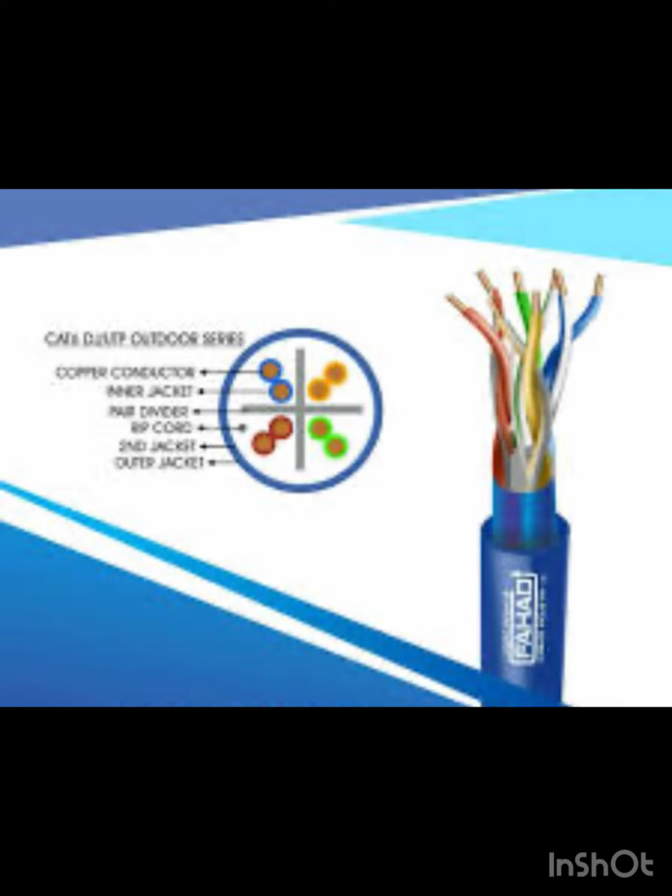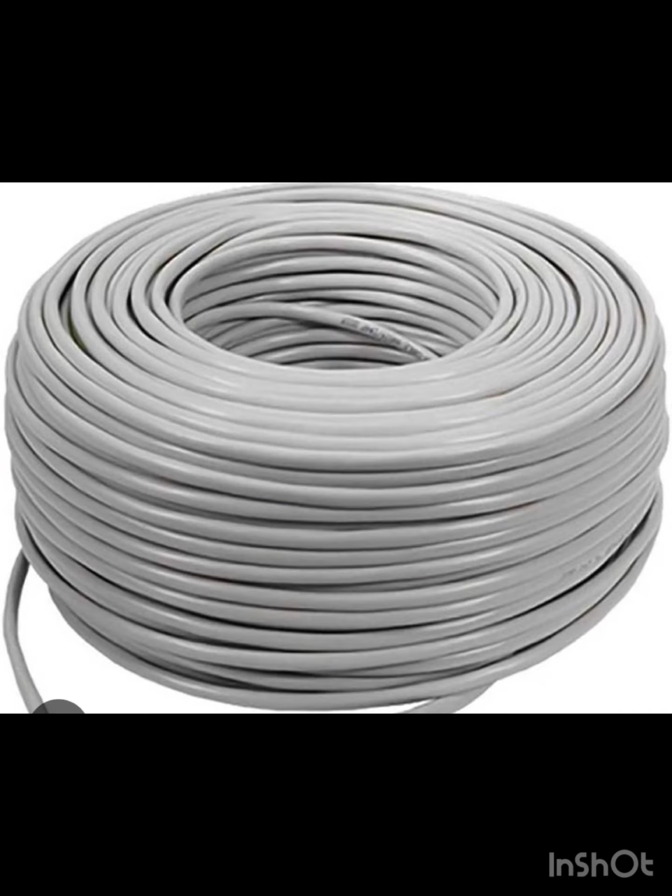So in order to check your Cat 6 cable, first check that the cables are correctly tagged. Based on that, a tag is required during your inspection. Check that they are installed and not stretched. Okay, so check the bending of the cables. It's very crucial: don't pinch and also don't bend the cables, and check the spare length of the cable.